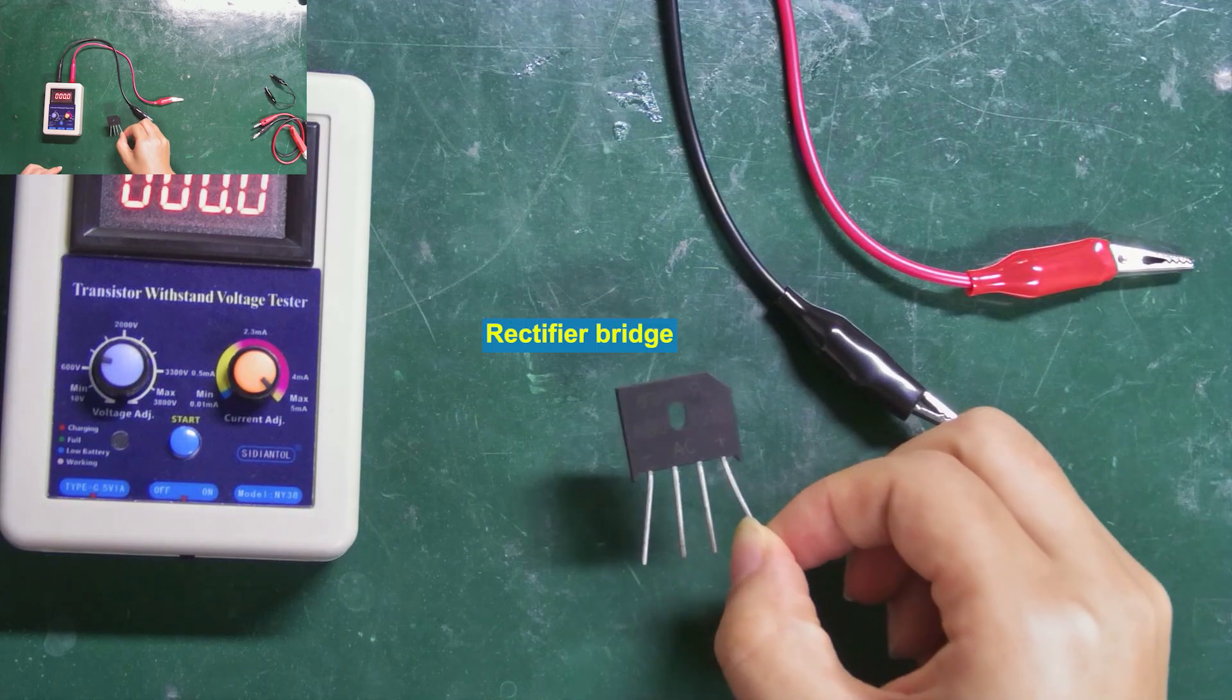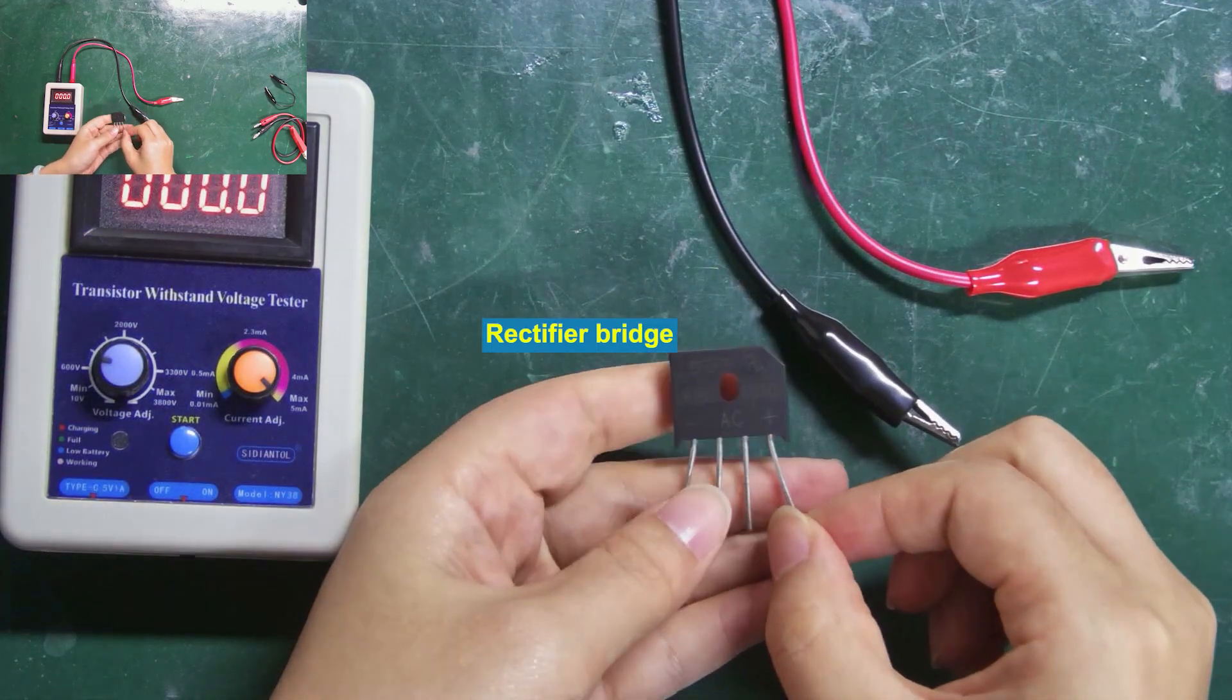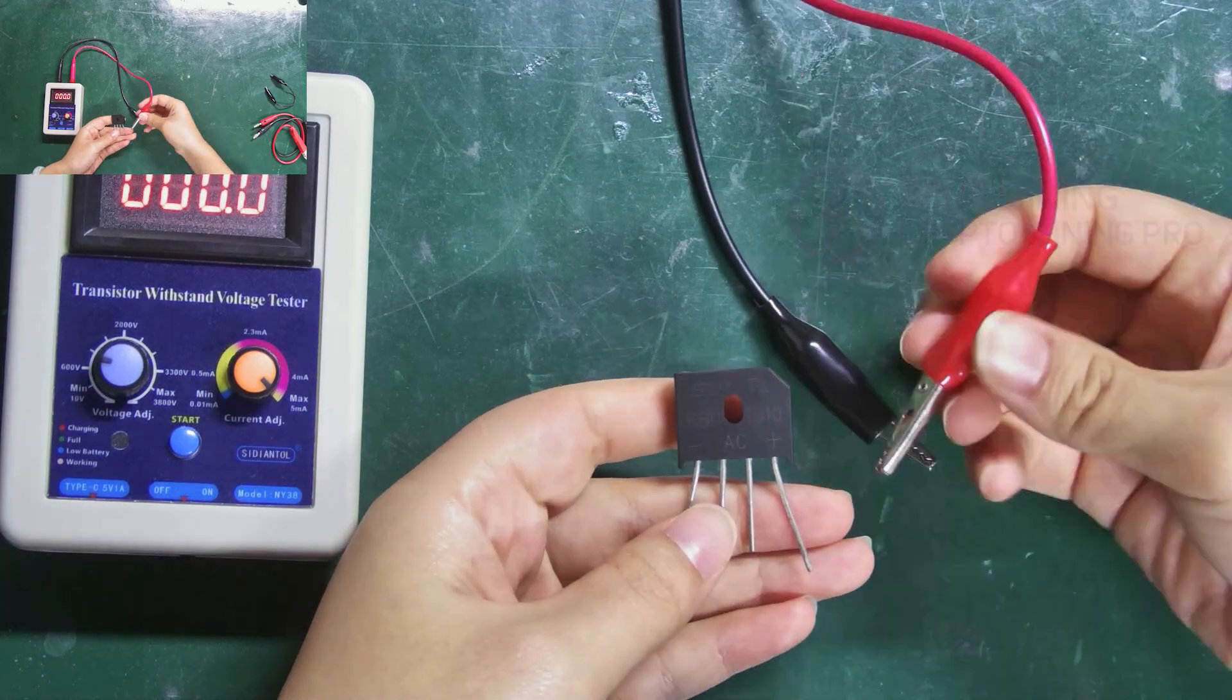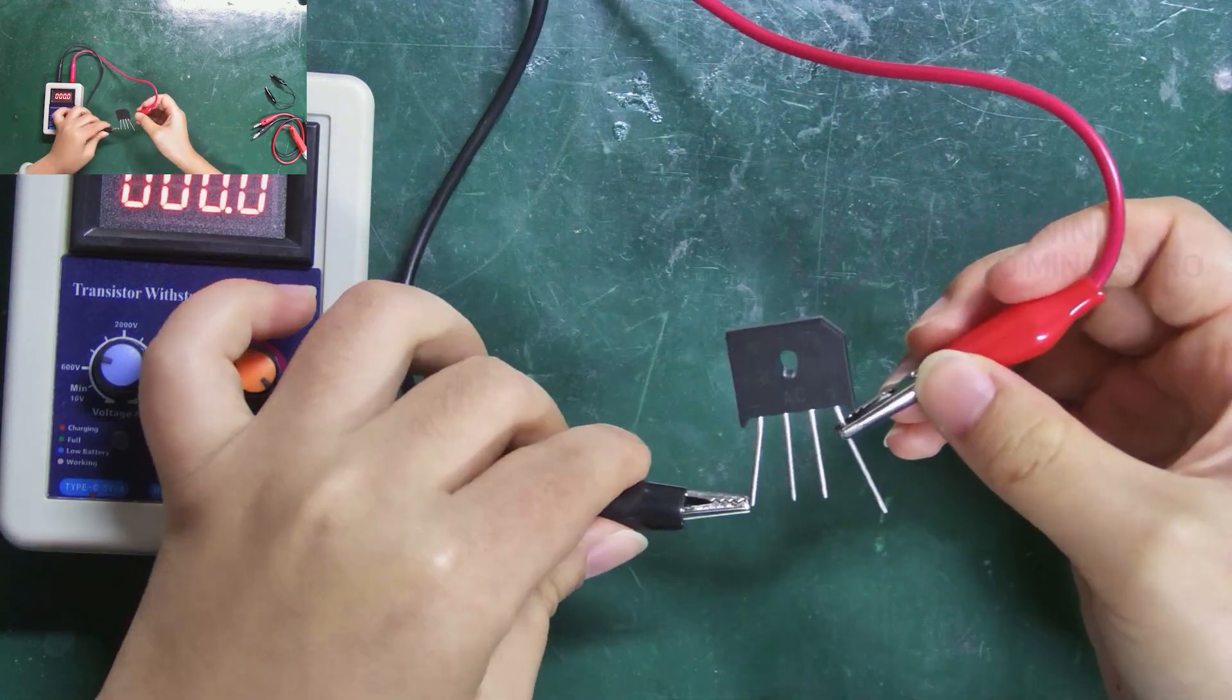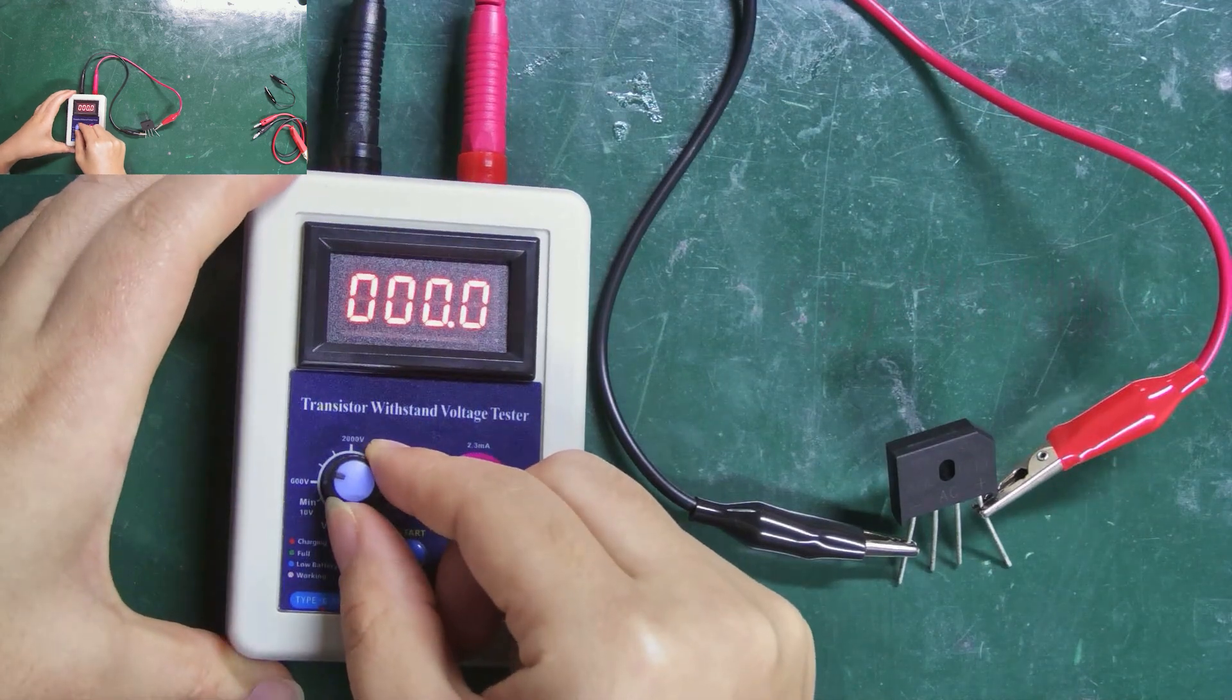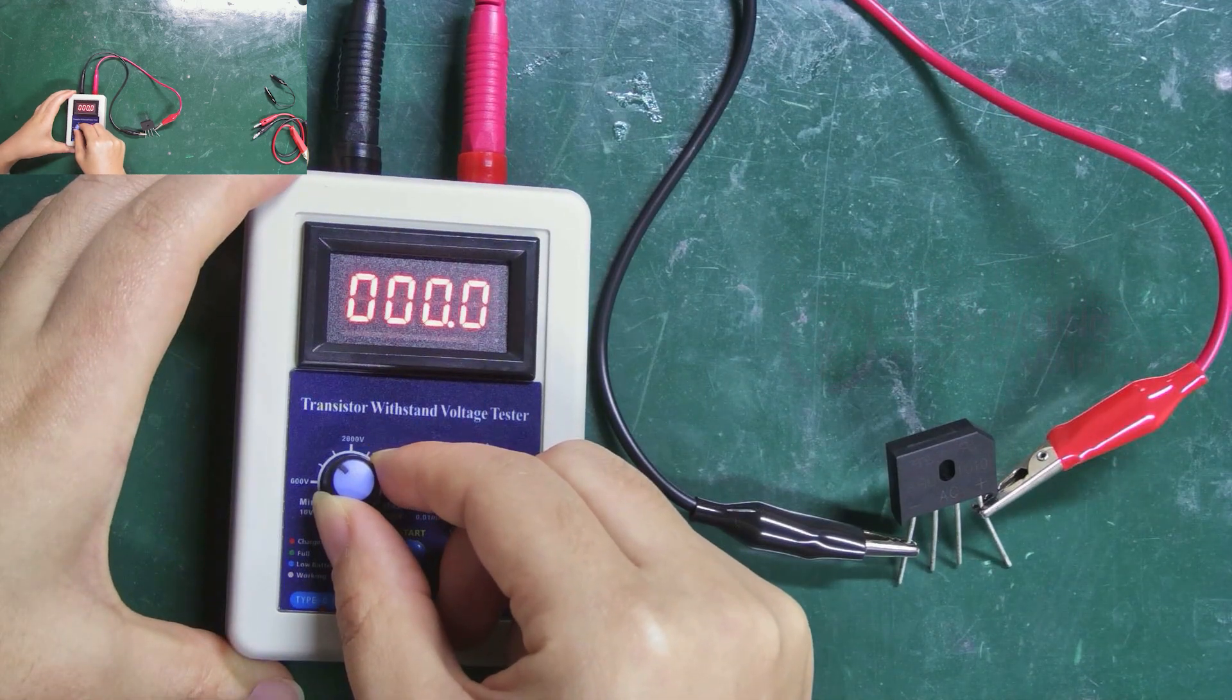Let's continue to measure this rectifier bridge, which is withstand voltage value for about 1000 volts. Connect the positive and negative poles. Then adjust the voltage to be greater than 1.5 times its withstand voltage value.